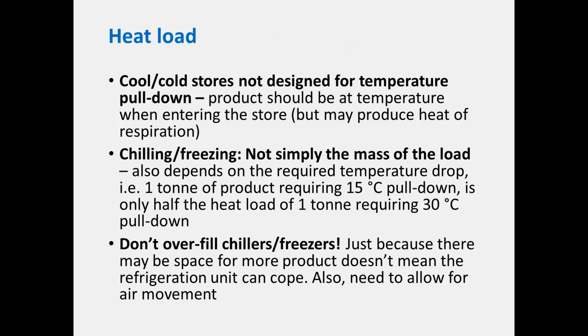So let's summarize some points about the heat load. It's important to recognize that cool and cold stores are not designed for temperature pull down. You get examples of refrigerated shipping containers being filled and then turned on, and sure enough, when the product gets to its destination port, it's spoiled. The refrigeration unit on a reefer container can handle a little bit of pull down, but it's really supposed to be loaded with product at temperature.